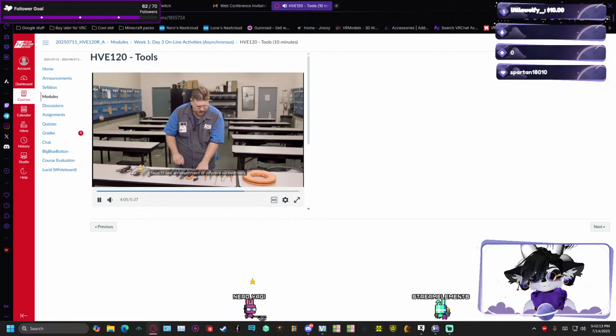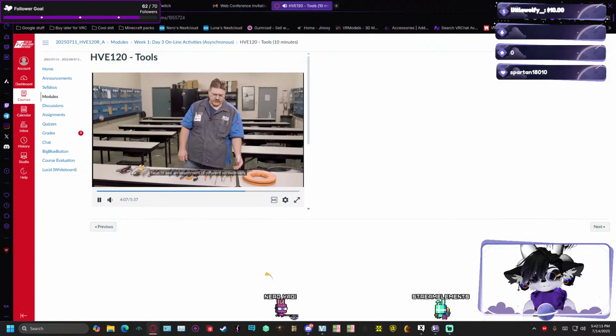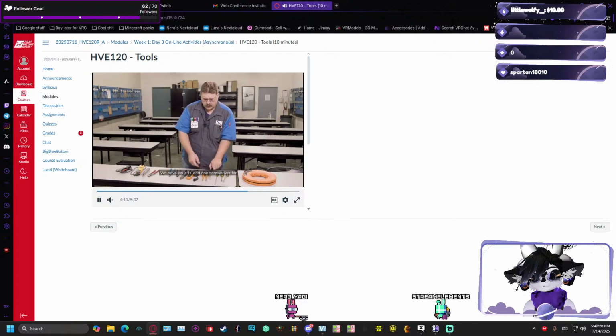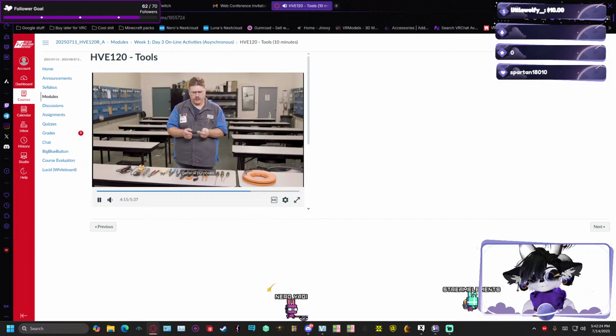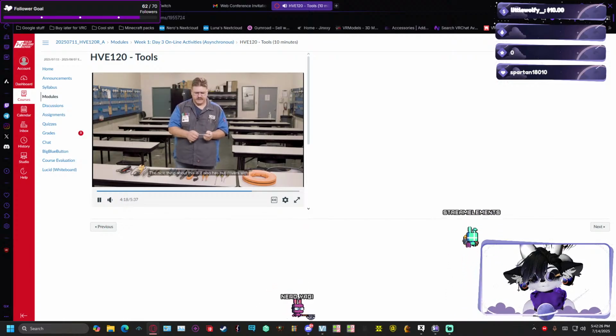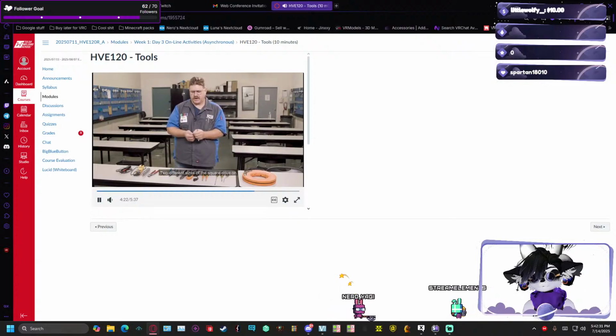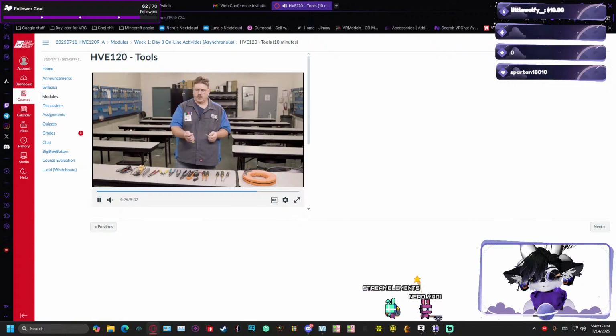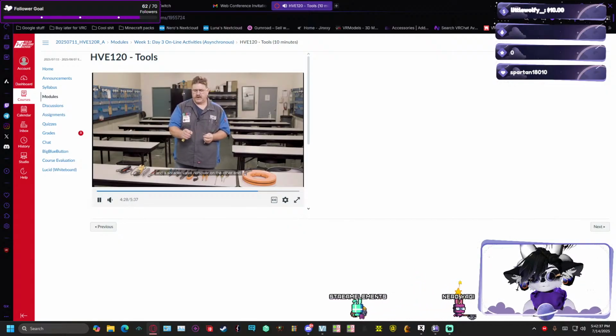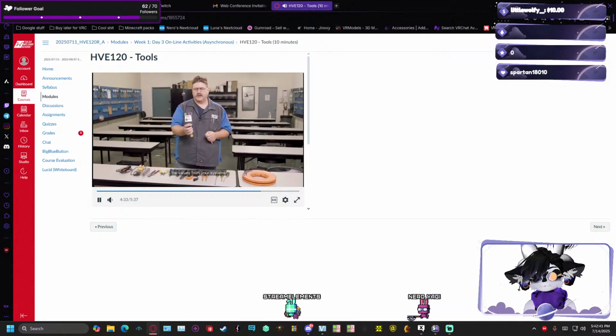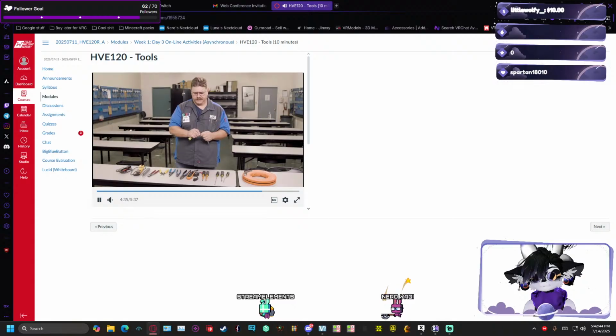Very handy tool. Next, you see an assortment of different screwdrivers. We have your insulated screwdrivers for your high voltage. We have your 11-in-1 screwdriver for general purposes. The nice thing about this is it also has nut drivers with it. Comes with nut drivers, has a square drive, 2 different sizes of square drive on it. Has a screw extractor on one end and a Schrader valve remover on the other end. That's good for you when you go to HVAC. You can remove the valves from your systems.